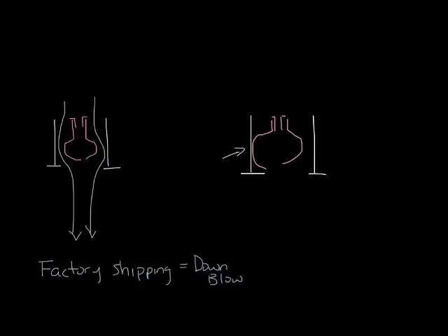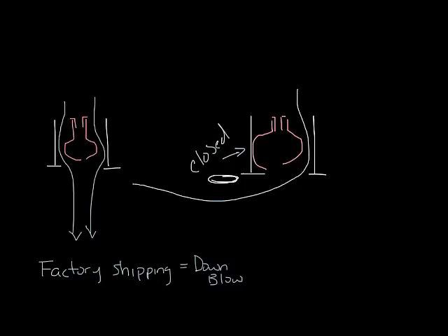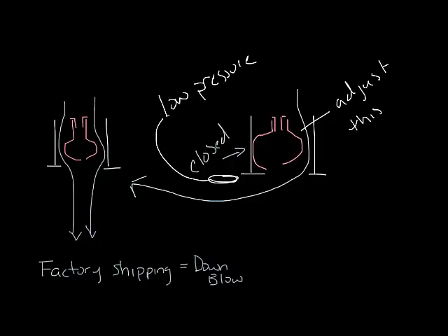What happens here is you're dampering one side, it's completely closed, so the air can't get by. And as the air comes out, you've got this low pressure zone right here next to the ceiling, and the air is going to come out and hold onto the ceiling and blow, in this case, to the left. By adjusting this pattern controller on the right, you can dampen how much air comes through the diffuser. So that's how the ML pattern controllers work.